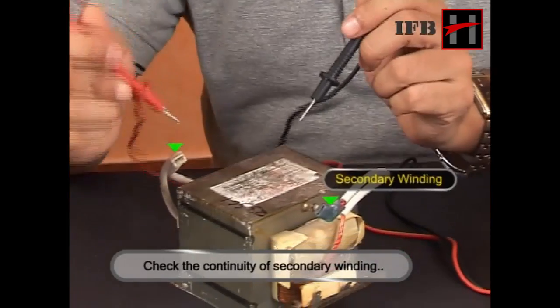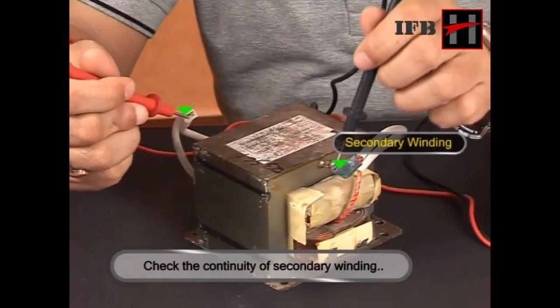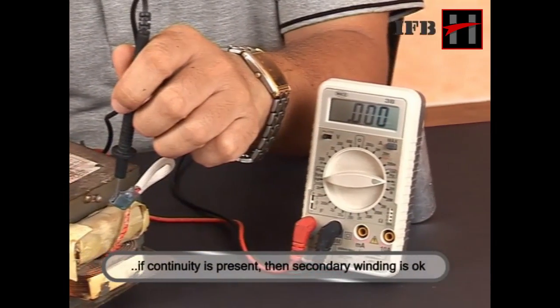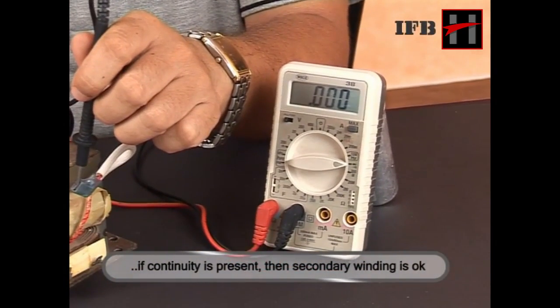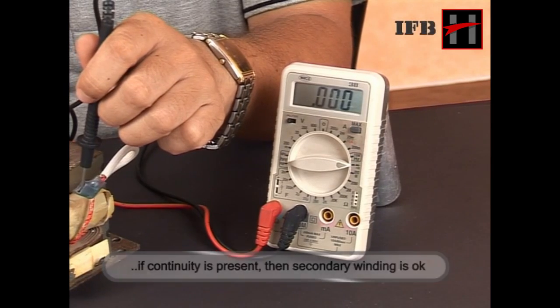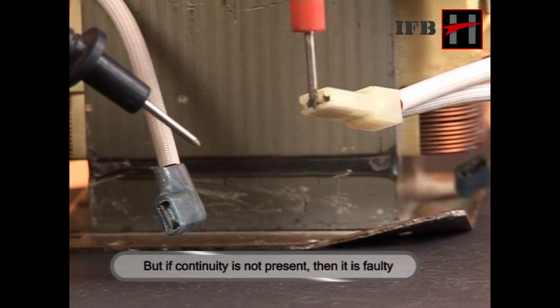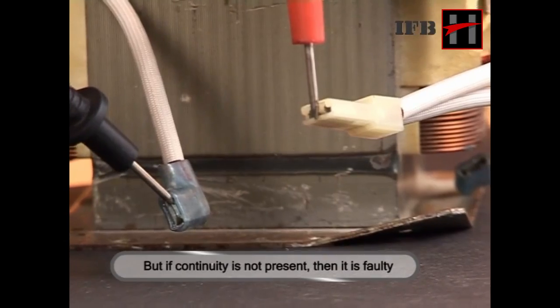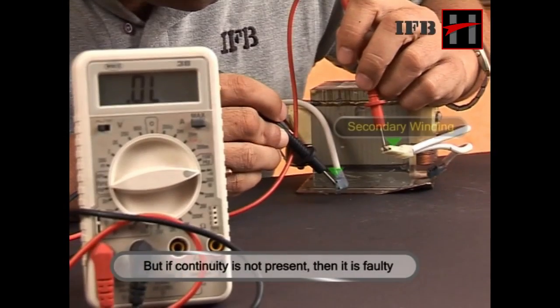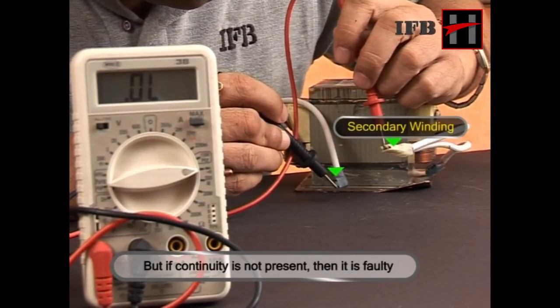Second, check the continuity on the secondary winding. If continuity is present, then the secondary winding is okay. But if continuity is not present, then the secondary winding is faulty.